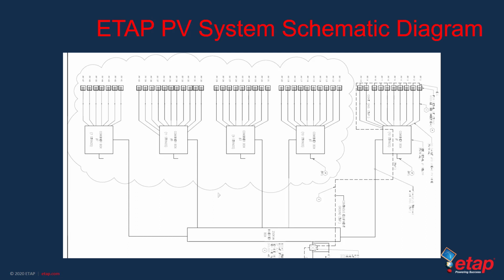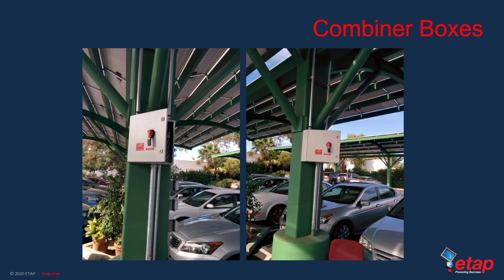The simulation that was performed using this software was done for 2 different arc flash analyses, one on the combiners and one for a fault at the inverter box. So our first fault will be location 1, which is one of the combiners, and our second fault will be at the inverter box, which is the second location. Here are some images of the combiner box locations that are scattered through the parking lot facility in our corporate building. The enclosure size is about 20 inch by 20 inch with a depth of 8 inches.